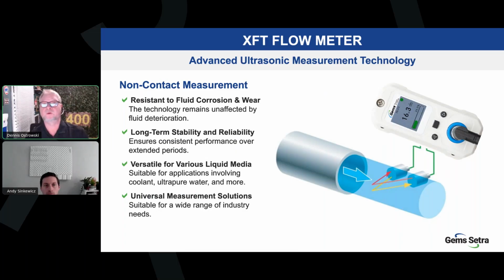Like I said before, you can order it for stainless steel, PVC, or PPR. However, when you program the device, it also gives you an other category. And when you do an other category, it then forces you to put in the acoustic velocity. You can find that online on Google. All of the pipe materials and all of the liquids, you can determine the acoustic velocity through those, and then change the parameters in the device itself.